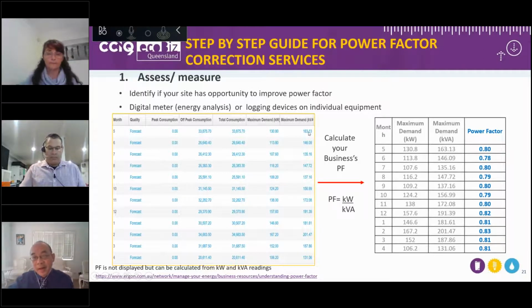When you divide one by the other, which you can see on the right-hand side, you can work out the power factor. While we don't currently have power factor calculations displayed, you can quite easily work it out yourself by dividing one by the other. The only thing to note is that if you have a lot of equipment all operating at once, the half hour of your maximum kVA demand may be slightly different to the half hour of your maximum kW demand. But if you have only one piece of equipment, then the half hours for maximum kW and kVA demand will tend to be at the same time.